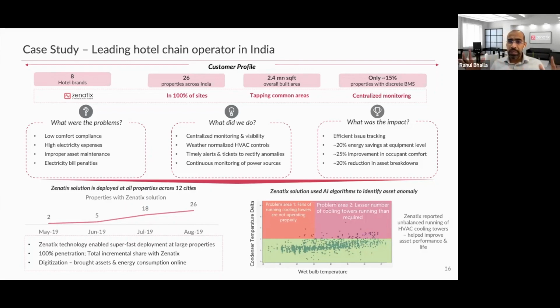There was a 25% improvement in guest comfort compliance. Guest compliance is easy to define: you define a temperature range, say 23 to 25 or 22 to 24, and that becomes your compliance - 1 to 4 degrees for a dairy chiller, minus 18 to minus 22 for a meat chiller. Then you see what percentage of the time you actually stay in that range, and that becomes your percentage compliance.